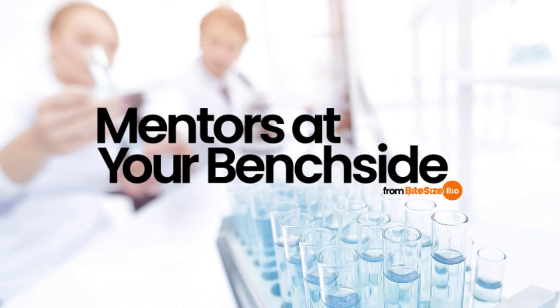Now, if you go to the original article, which you can find in the episode description, there will be an image that shows the pan of a scale with the samples placed in 9 different locations, 1 exactly in the middle, and then 8 in a circle around it. So these are the different locations on the pan where you should be able to get the same value when you put your sample there. And again, look at the range to tell you how consistently your scales are weighing your samples across these different pan positions. And the third test you can do is the linearity test.